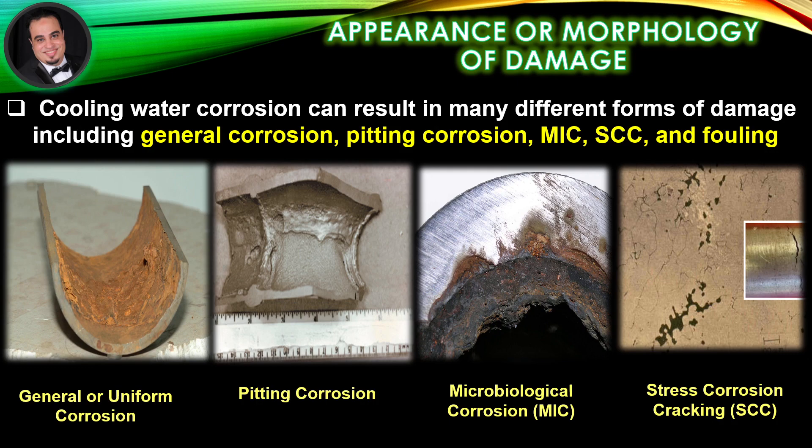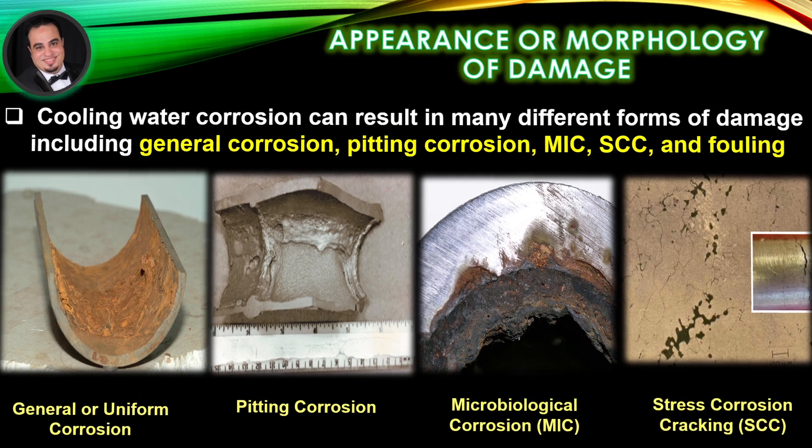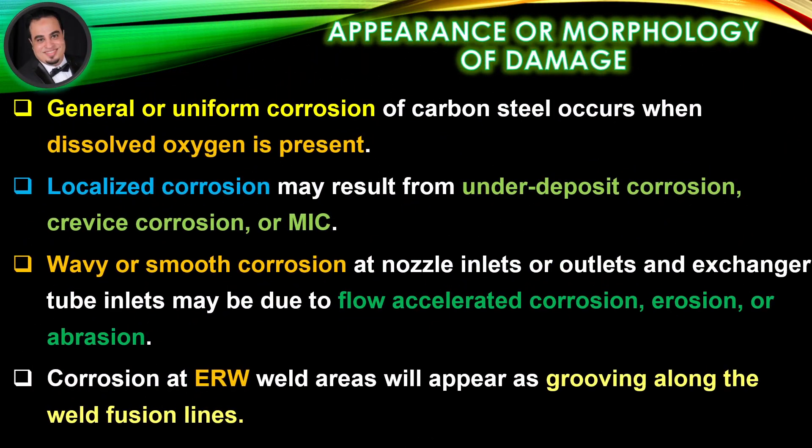Forms of damage also include microbiological corrosion, stress corrosion cracking, and fouling. General or uniform corrosion of carbon steel occurs when dissolved oxygen is present. Localized corrosion may result from under-deposit corrosion, crevice corrosion, or microbiological corrosion. Wavy or smooth corrosion at nozzle inlets or outlets and exchanger tube inlets may be due to flow-accelerated corrosion, erosion, or abrasion. Corrosion at electric resistance welding weld areas will appear as grooving along the weld fusion lines.